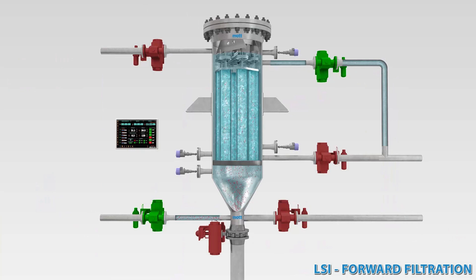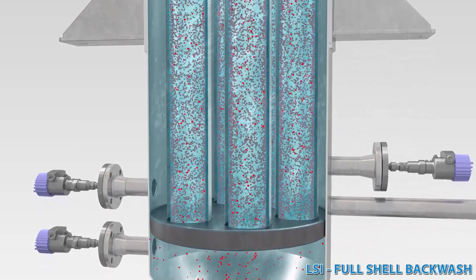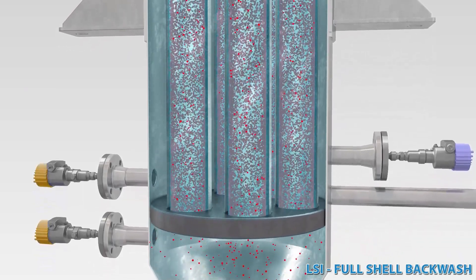Forward filtration continues until the differential pressure setpoint is reached, the cycle time setpoint is reached, or an operator interfaces with the control system to force a backwash.